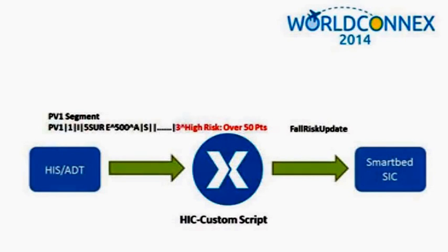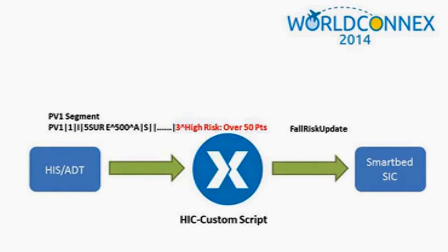Here's an example of an ADT message that contains the fall risk score. That information, available in the HIS ADT, can be retrieved by Connexall, which in turn communicates it to the Stryker smart bed component and automatically updates the bed profile with the correct fall risk.